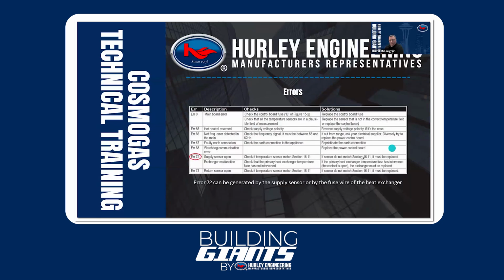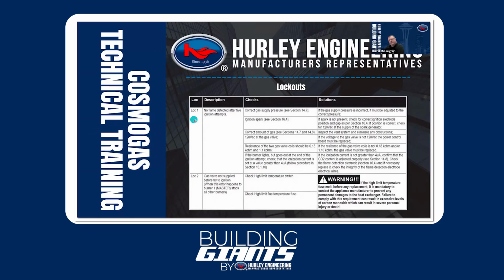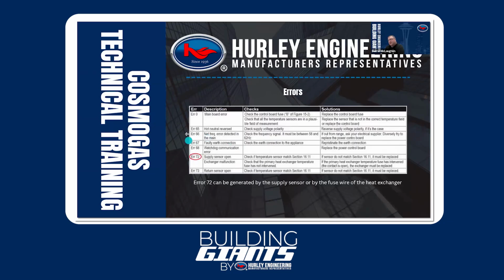We've also got these errors, and this is the one I wanted to bring up from earlier: error 72. The difference is, if I go back here, LOC is going to be a lockout. That's something I'm going to physically have to reset most of the time, or all of the time. Error codes will generally correct themselves once the condition has changed. What I mean by that is if we look at, let's say, the second one here, error 65, supply voltage polarity. If we've got the polarity wrong, as soon as we change that polarity, the error 65 will go away. We shouldn't have to reset it.